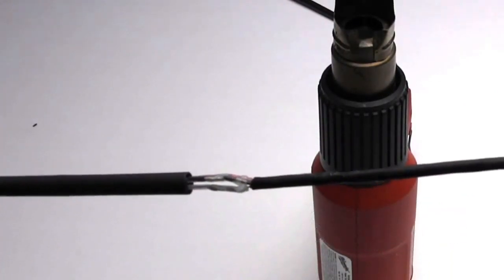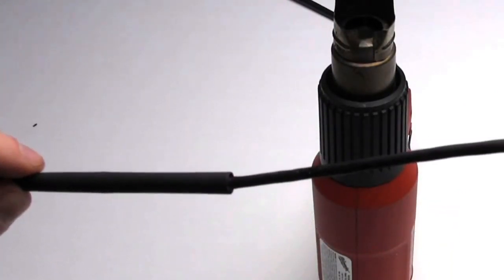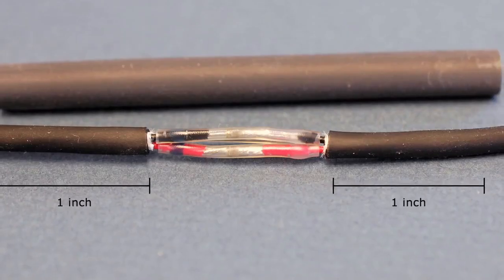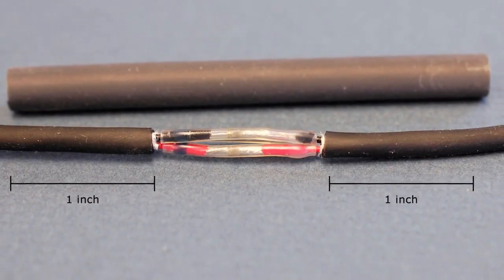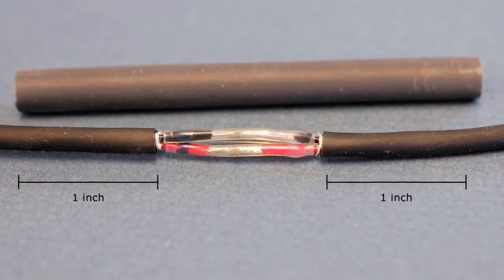For step 6, slide the polyolefin adhesive lined heat shrink over the junction of the wires. This will seal the splice from the elements. Allow an extra one inch of coverage by the heat shrink on the outer jacket of cable to ensure a good seal.